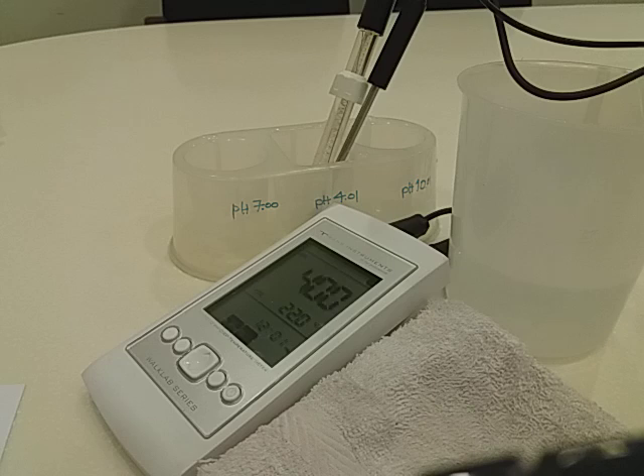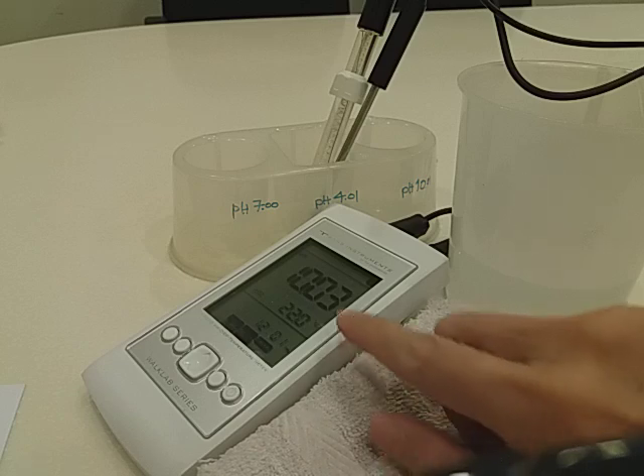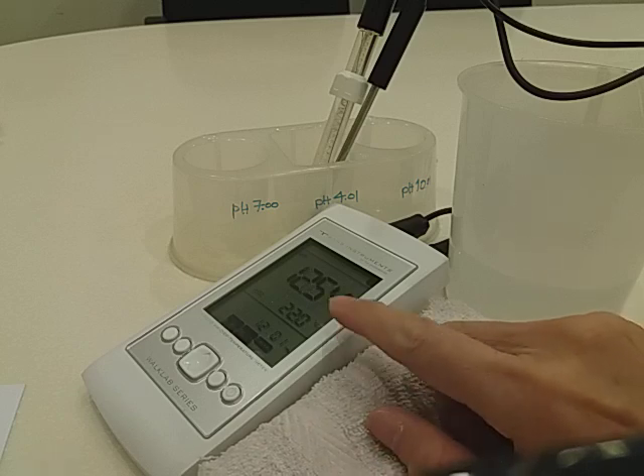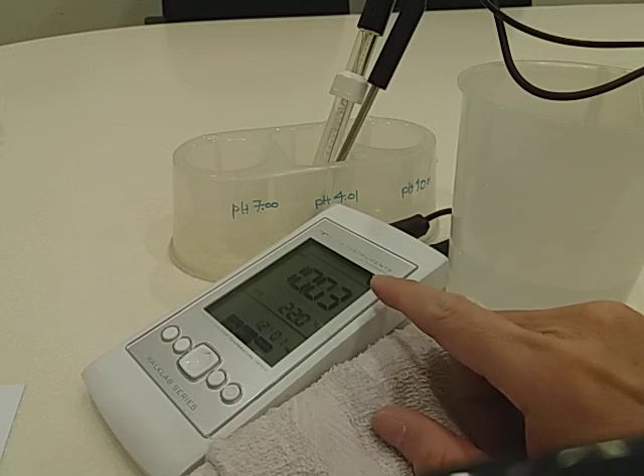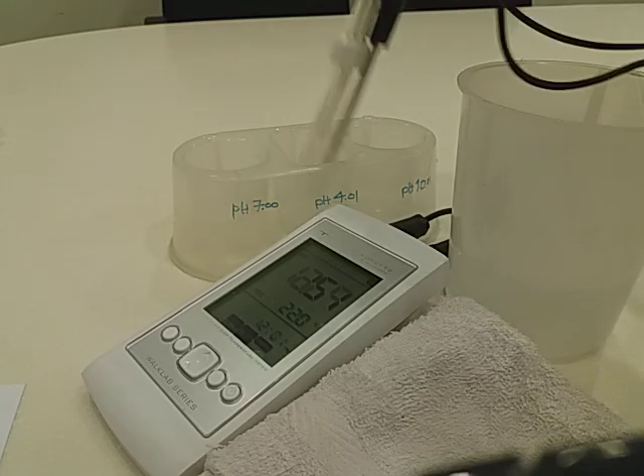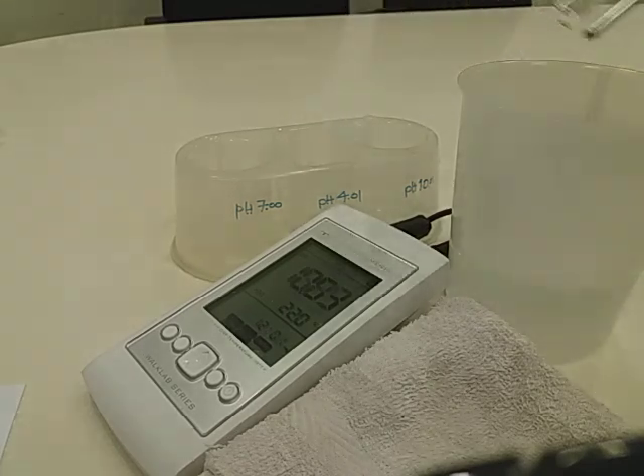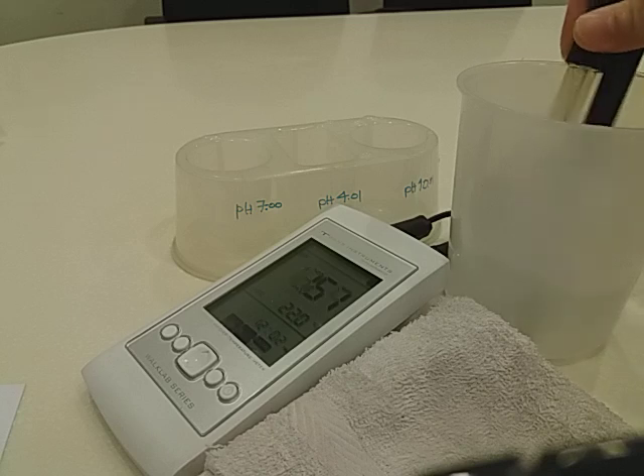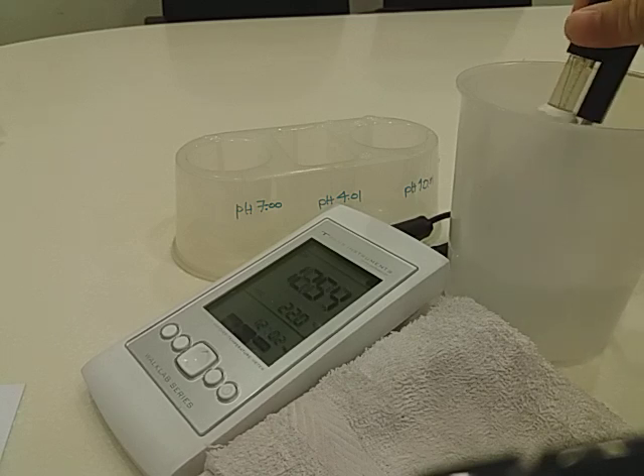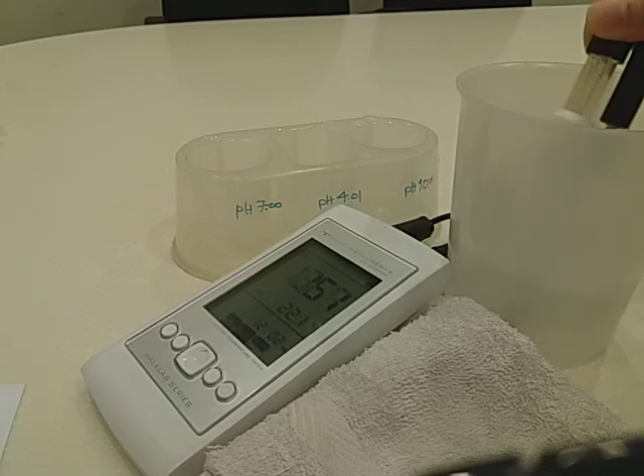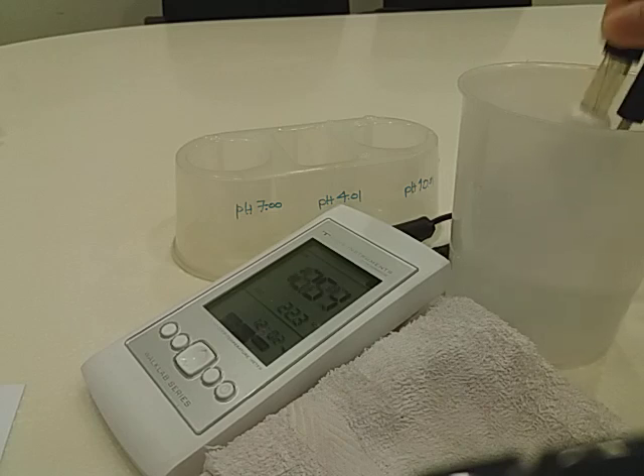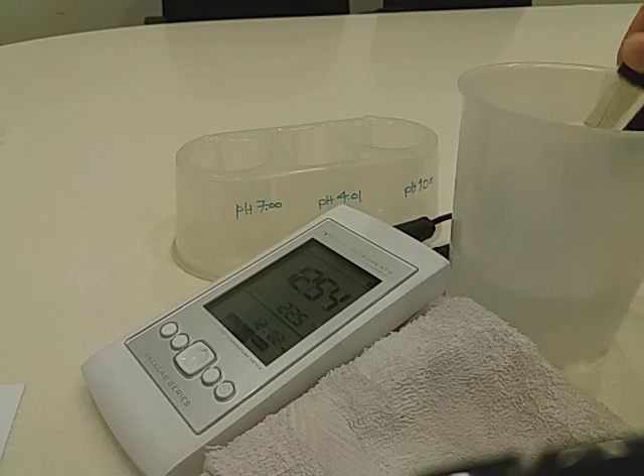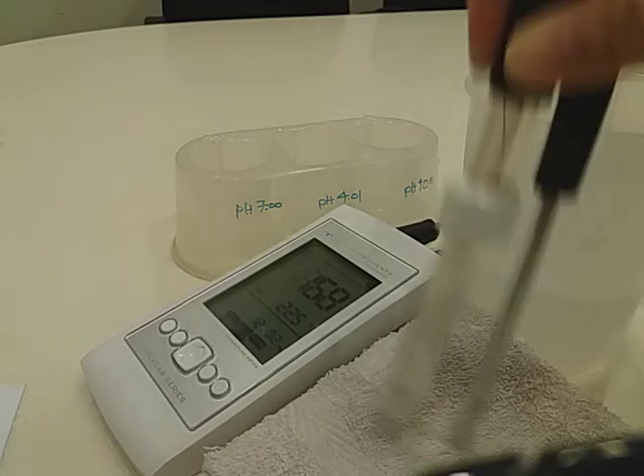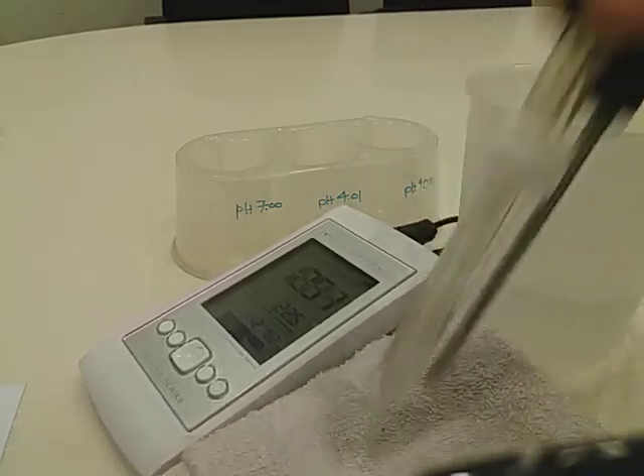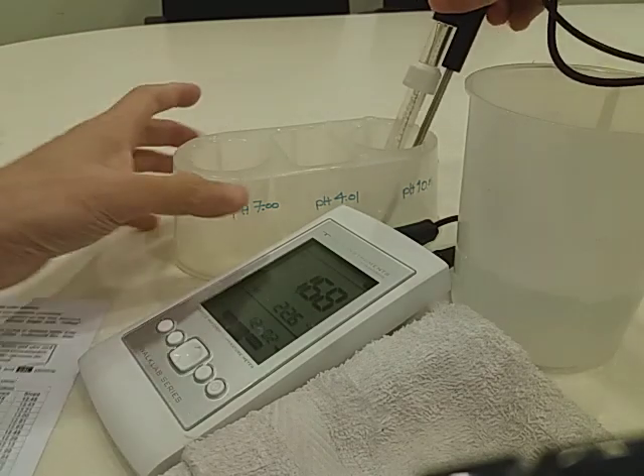So again, the meter will establish a stabilized reading. Then it will ask you for the rest of the calibration buffer. Again, rinse the electrode thoroughly in distilled water. Dab dry. Then put into pH 10 solution.